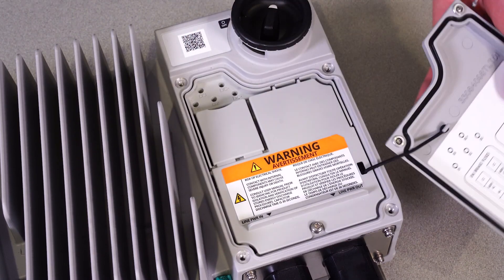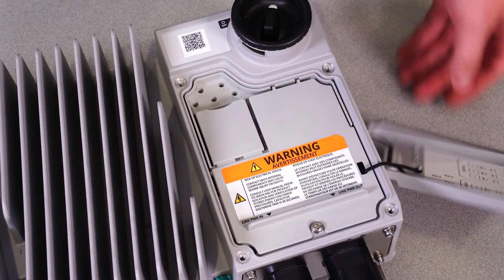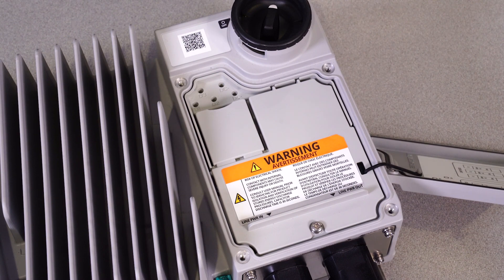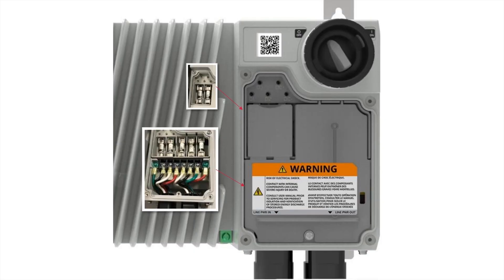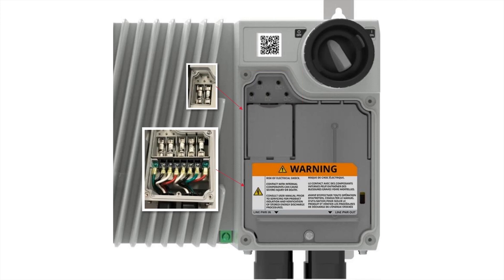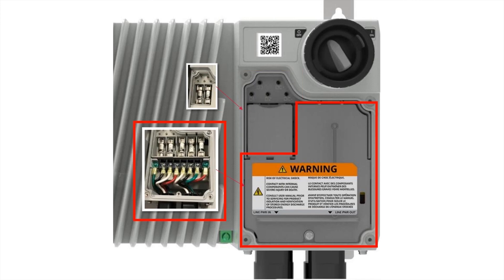If we remove the cover of the power section of the drive, we gain access to some of the electrical components. Under the cover, we can see test points for the DC bus. Below these, we have the fuses for the EM brake, and finally, taking up the bulk of the power control section is the line side branch protection circuit.